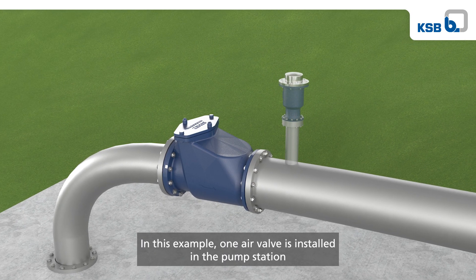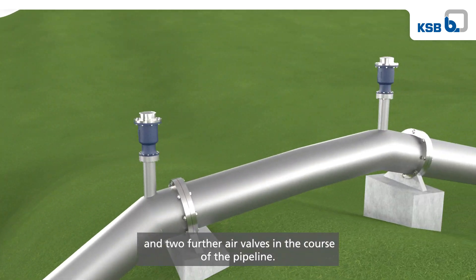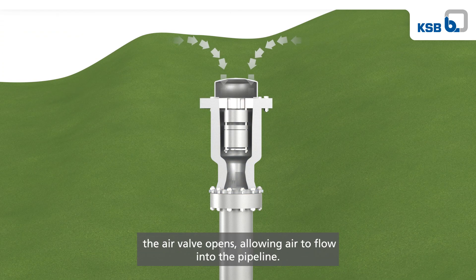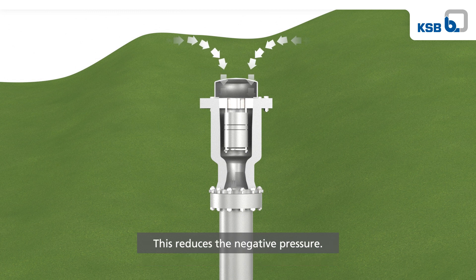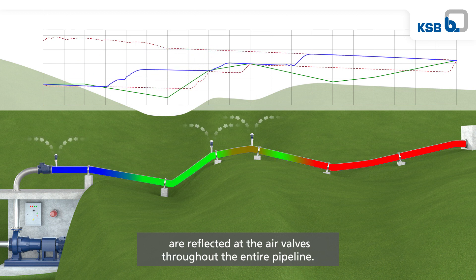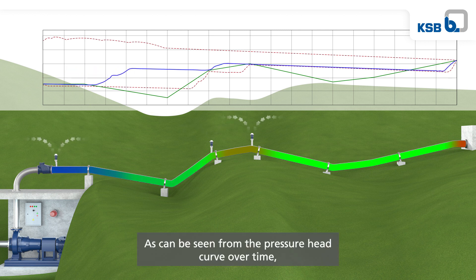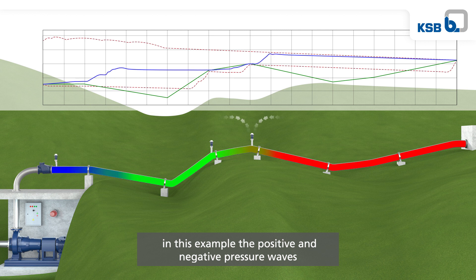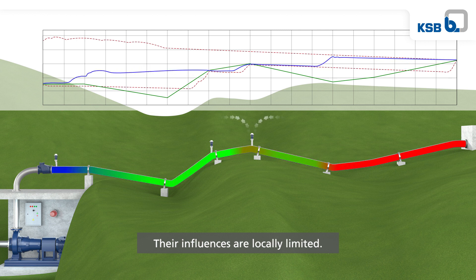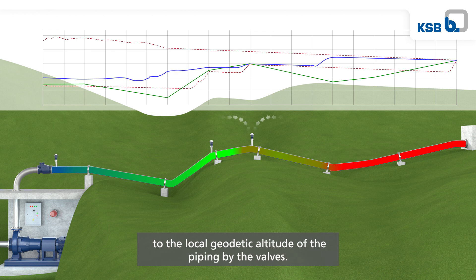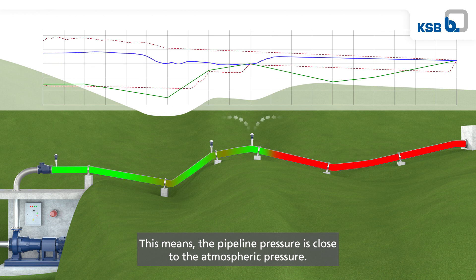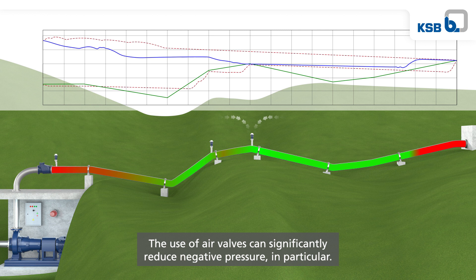In this example, one air valve is installed in the pump station and two further air valves in the course of the pipeline. In the case of negative pressure, the air valve opens, allowing air to flow into the pipeline, which reduces the negative pressure. The positive and negative pressure waves of the pressure head curve are reflected at the air valves throughout the entire pipeline. As can be seen from the pressure head curve over time, in this example the positive and negative pressure waves run back and forth between the valves, with their influences locally limited. The pressure head curve is adjusted to the local geodetic altitude of the piping by the valves, meaning the pipeline pressure is close to atmospheric pressure. The use of air valves can significantly reduce negative pressure in particular.